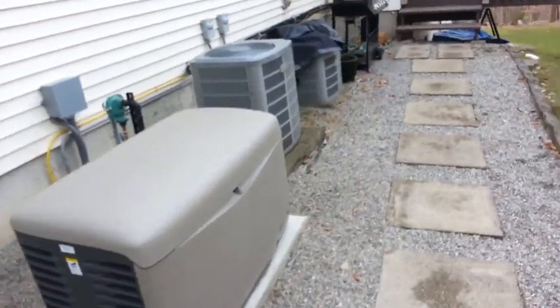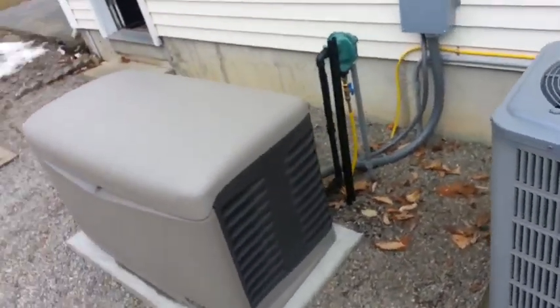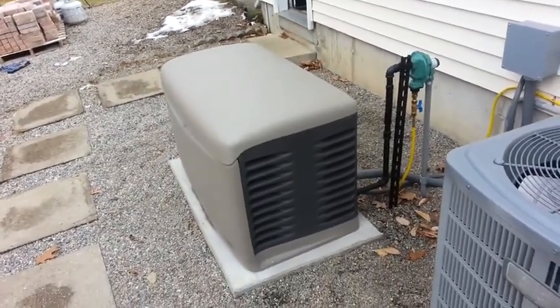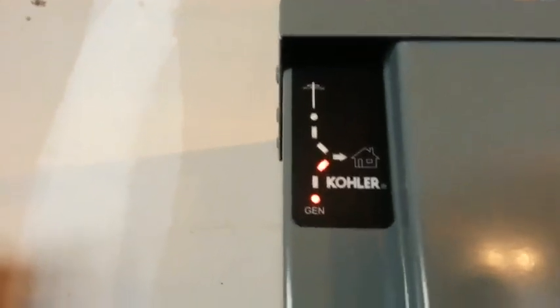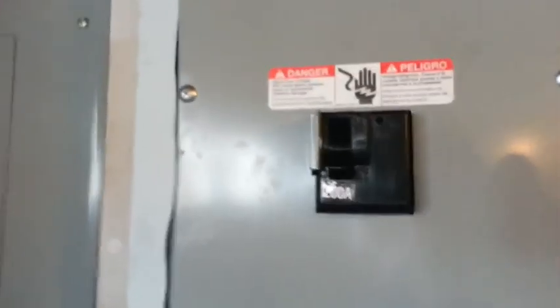I just got an email. There's our power. And there we go. It's a lot louder in this video, I apologize, but it's not that loud in person. Go inside. Lights on like normal. No flickering whatsoever. Acting completely normal, like if it was utility grade power. And as you can see here, like I said, we're now operating off the generator because my main utility feed is off.